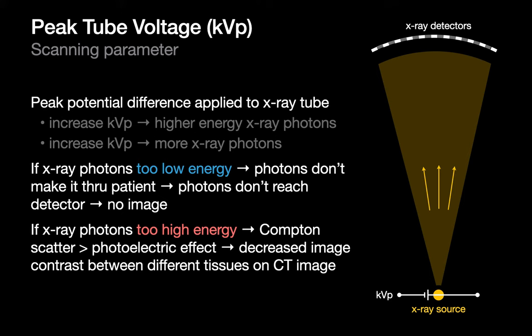Peak tube voltage (KVP) influences the energy each individual x-ray photon carries. The higher the KVP, the more energy packaged in each photon. Too little energy and photons don't make it through the patient — not enough hit the detector to form an image. With too much energy, the detector collects lots of photons, but the relative ability of different materials to block x-rays — like water versus muscle — becomes similar, so image contrast and ability to distinguish tissue types suffers.